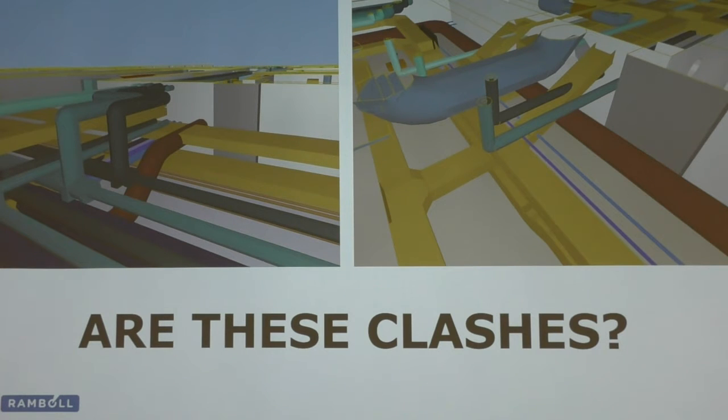Was it the BG6 document earlier that said it has to be maintainable and installable? Yes. You have to look at the sequencing. But I'm just trying to highlight the things hitting in a clash detection report. The question is, could you displace that out a bit more to get a bit more access? How does that fit? So you could argue, generically feasible, that that's not a clash.